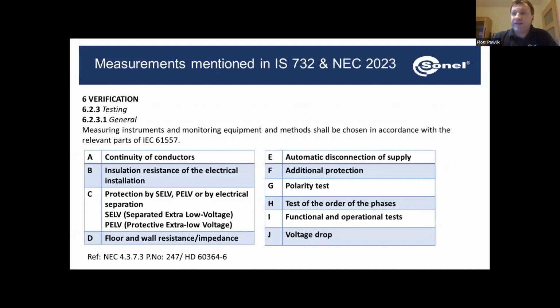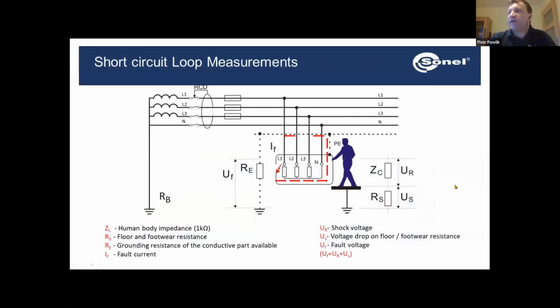And we can see here what measurements we need to do when we want to verify our electrical installation. Probably you are familiar with these measurements, but the new things that we can find over here are the resistance of floors and walls and the automatic disconnection of supply. Right now, quickly, when will we need to disconnect the supply automatically? In case we have a fault situation and there will be a short between a phase channel and the ground, then we're going to have some dangerous currents flowing through the protective channel to earth, or there will be a possibility of electric shock to a person who's going to touch the faulty elements.